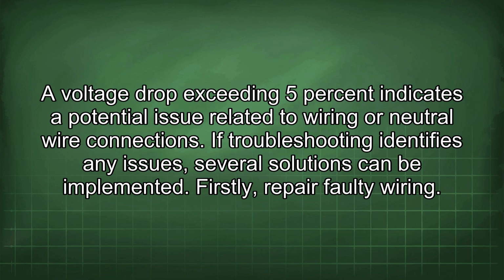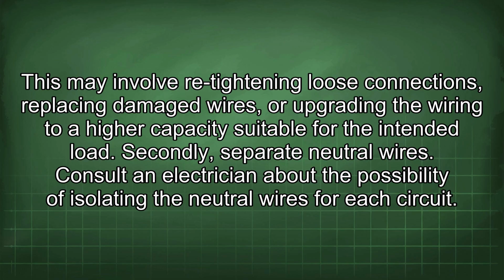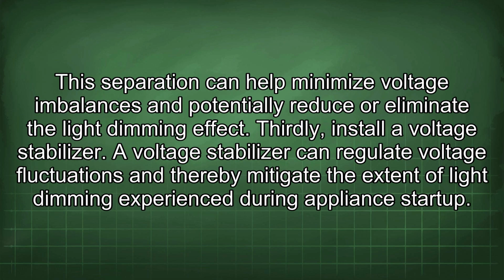If troubleshooting identifies any issues, several solutions can be implemented. Firstly, repair faulty wiring. This may involve retightening loose connections, replacing damaged wires, or upgrading the wiring to a higher capacity suitable for the intended load. Secondly, separate neutral wires. Consult an electrician about the possibility of isolating the neutral wires for each circuit. This separation can help minimize voltage imbalances and potentially reduce or eliminate the light dimming effect.